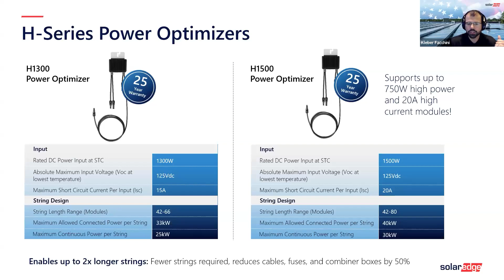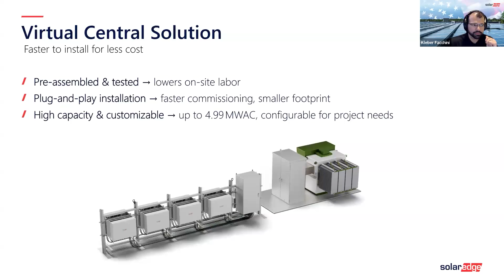Last slide on TerraMax: we also have what we call the virtual central solution, where you're putting up to 5 megawatt AC blocks. We have 1 megawatt and 2.5 megawatt AC standard blocks that are pre-wired and delivered to the field. The inverters are delivered on a rack already wired, ready to be connected to your AC switch gear and then to the transformer. Reach out to us for more details; blocks go up to 5 megawatts AC, with a 4.99 megawatt AC option, since a lot of folks limit to 5 megawatt AC so they don't trigger a more complicated interconnection study. There were also some grants available for projects less than 5 megawatts AC, so that's why we designed that version.